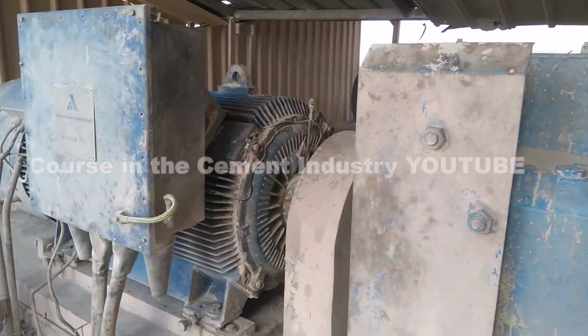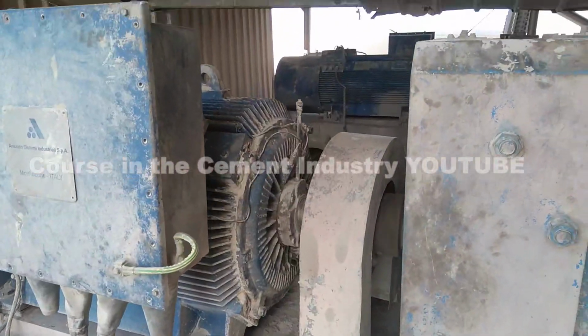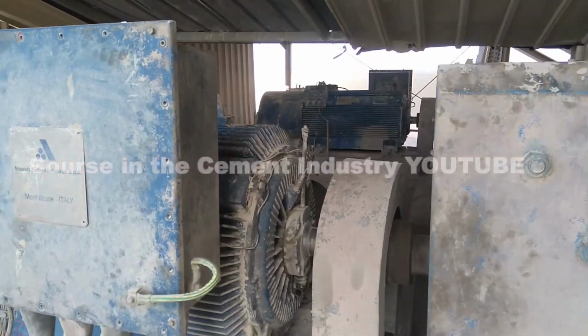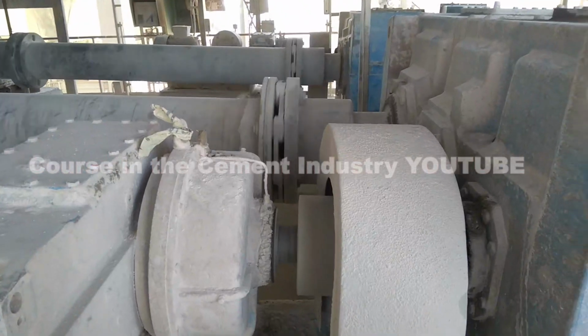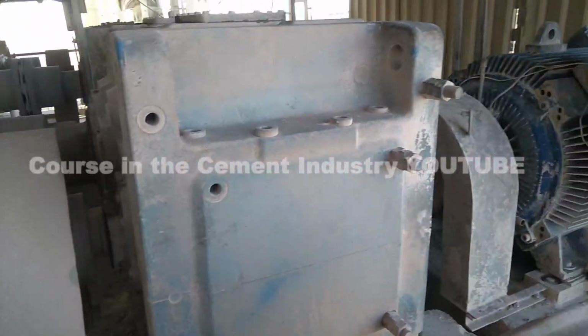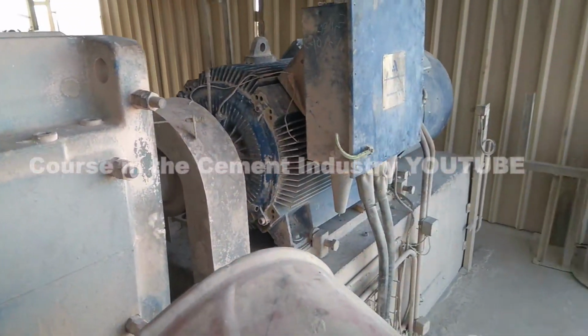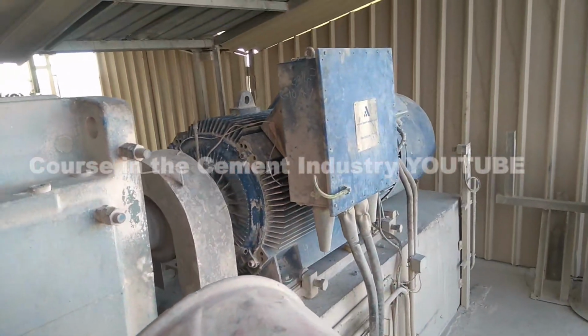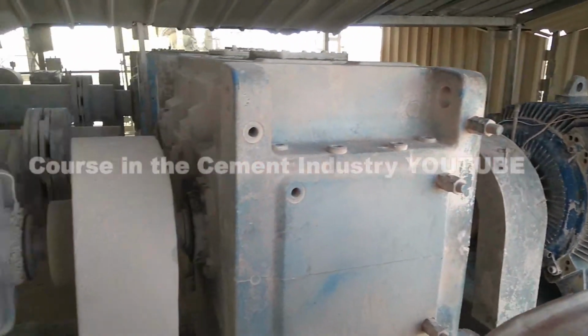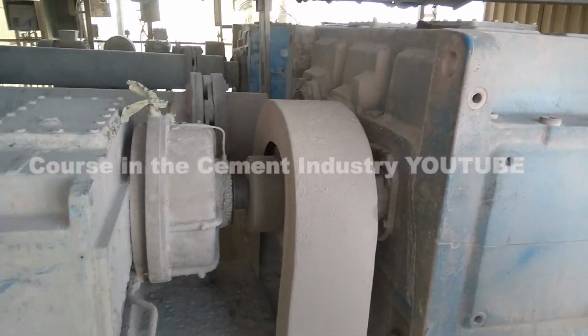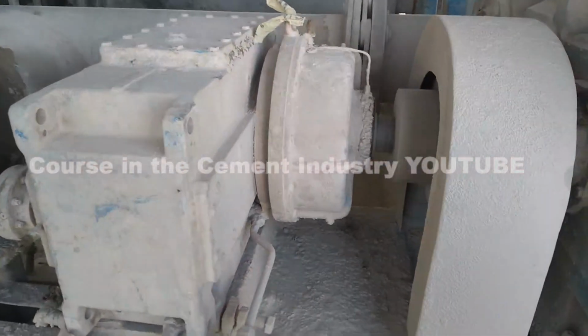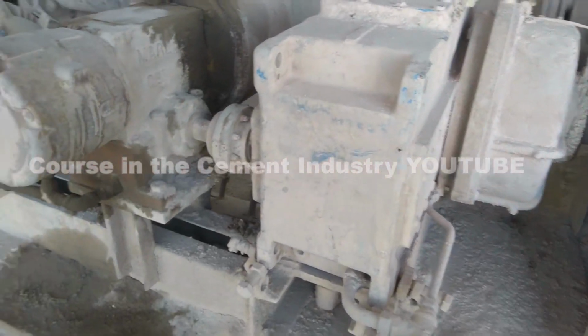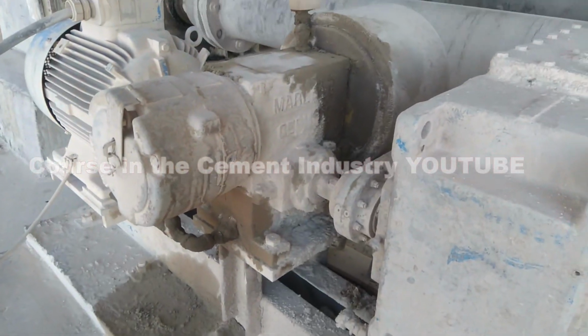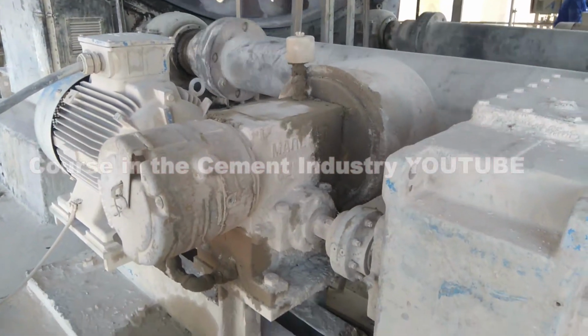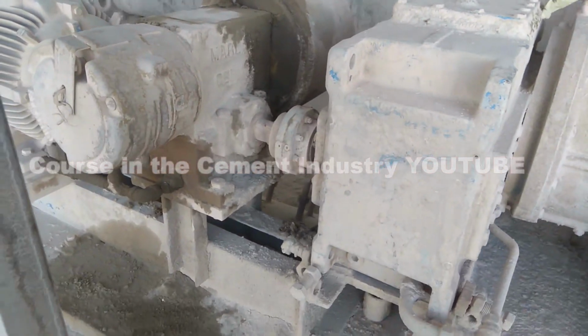C. Operational protection, interlocks. The main drive will automatically trip, shut down, if: 1. The lubrication oil pressure drops. 2. The gearbox or motor temperature exceeds safety limits. 3. The rotary kiln thrust, longitudinal movement, is too high. 4. The auxiliary drive is still engaged.